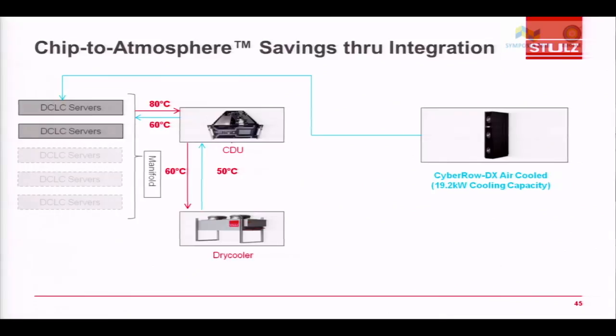When you do the integration, it's very important to see that we are not anymore talking of cold climates, cold countries, where ambients are 10 degrees, 20 degrees or 0 degrees. This is for a country like India, where we have 43 degrees ambient temperatures, because there is no cold water anymore. You are having water which is cooling the servers at 60 and 80. It's not 6 and 8. 60 and 80 is the water temperature which is required to cool. And when you have 60 degrees water to be cooled, a normal atmospheric dry cooler with an ambient of say 40, 41 degrees could be sized and would be good enough to give you the return water.